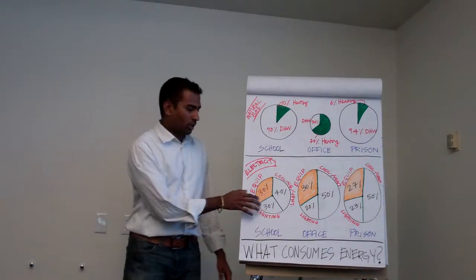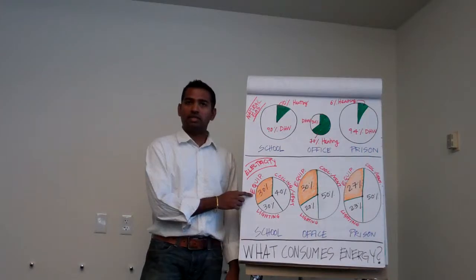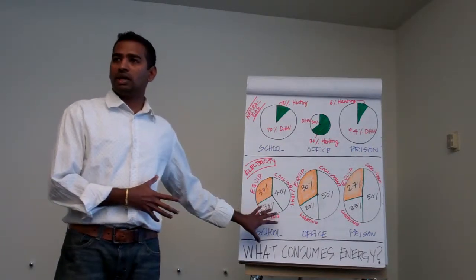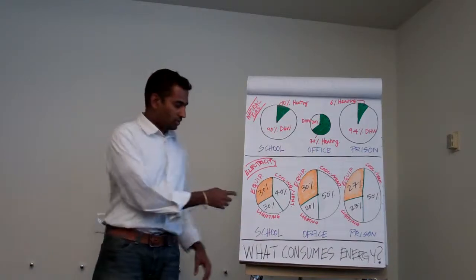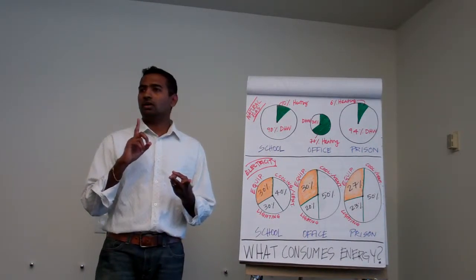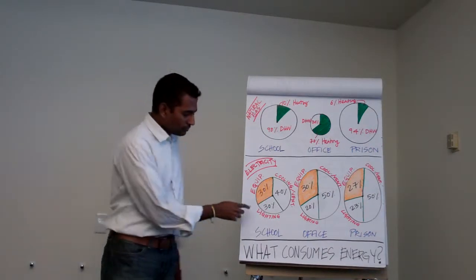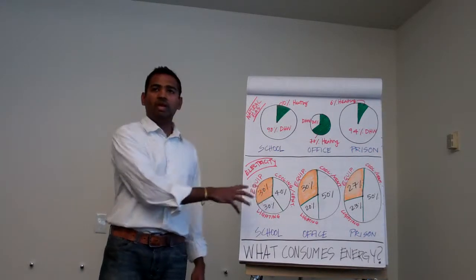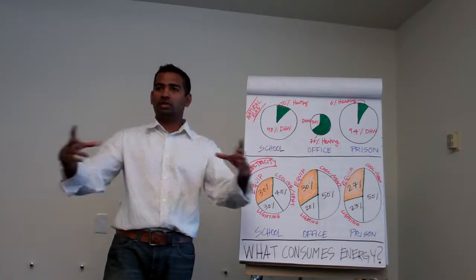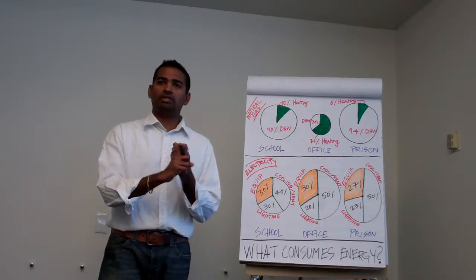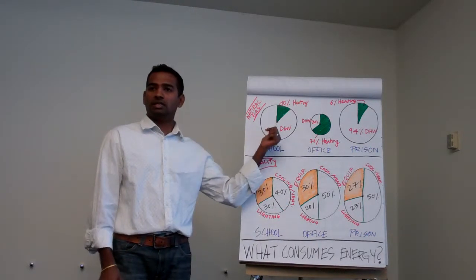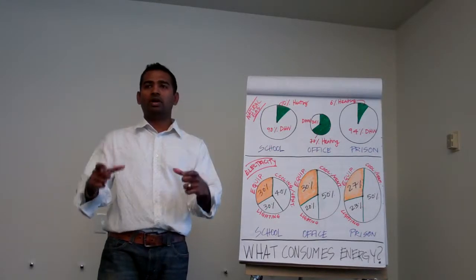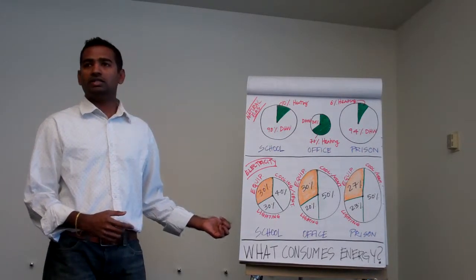Right, and I'm going to talk about how we, as design professionals, can impact this, because this is assuming a certain number of PCs and equipment for this building type. We can help the clients reduce this through using Energy Star equipment, flat monitors and so on. We'll talk about that later under energy modeling. But it's important to understand the breakdown. This breakdown may change slightly based on how you position your building, and it could change based on your zip code, because the cooling energy and the heating energy change a lot. So it's very important to have a simple box of your building square footage, put in your zip code, and find out what the energy breakdown is.